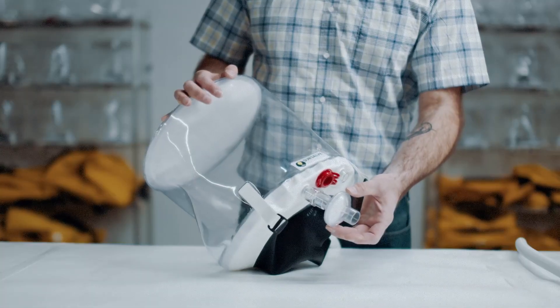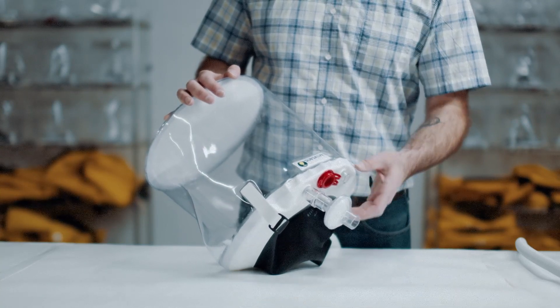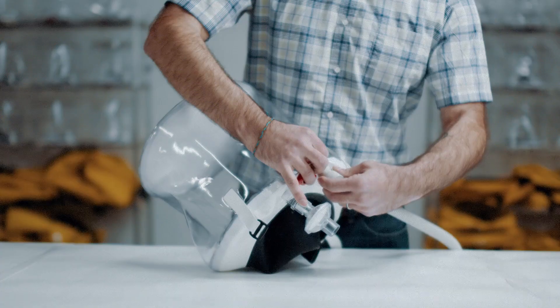This is a filter that is either N95 or equivalent, which means that as the air supply passes through the helmet, the patient's exhalations are vented through the filter. So in addition to being therapeutically beneficial for the patient, we're also protecting the healthcare workers by limiting the amount of virus that escapes into the work environment.